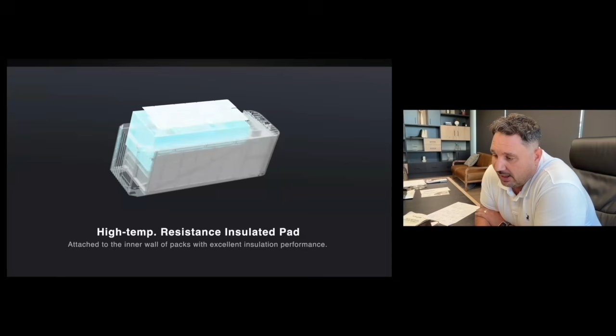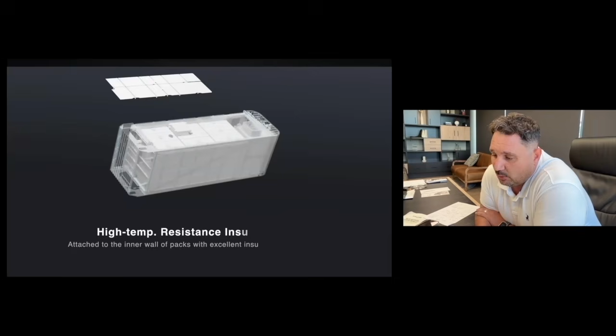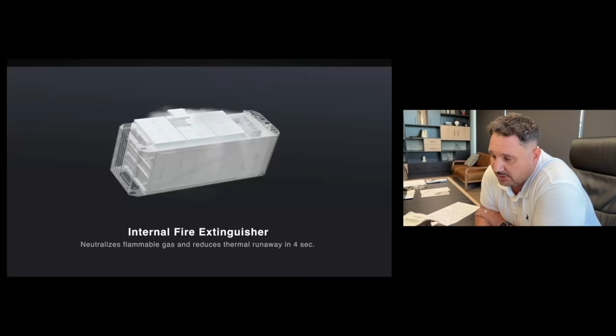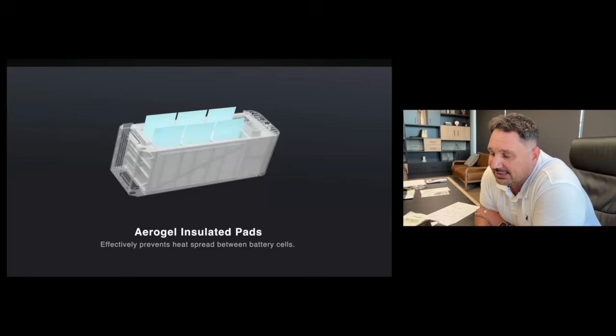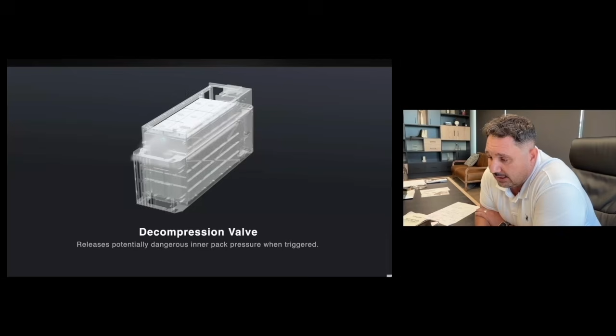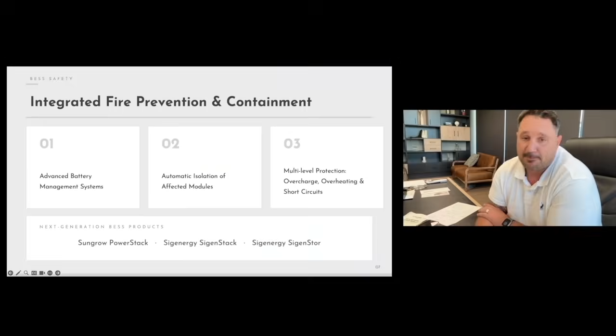So there's 5 layers of battery safety protection built inside each battery block. So first of all, you have high temperature insulation pads that are attached to the inner walls of the packs. You have an internal fire extinguisher which neutralizes flammable gas in 4 seconds. Aerogel pads, which prevent heat being spread from one cell to the next, which is one of Anthony's concerns. A decompression valve to let dangerous inner pack gases expand. And then 7 temperature sensors that monitor temperature all across the cells to make sure that thermal runaway does not happen.